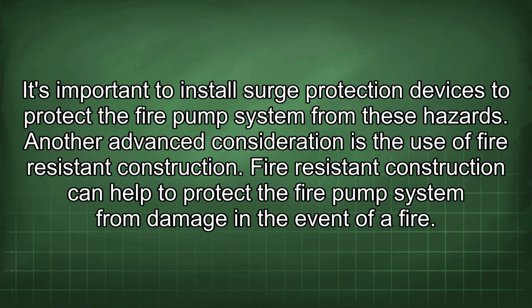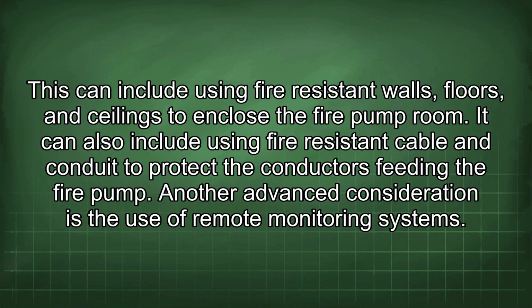Another advanced consideration is the use of fire-resistant construction. Fire-resistant construction can help to protect the fire pump system from damage in the event of a fire. This can include using fire-resistant walls, floors, and ceilings to enclose the fire pump room. It can also include using fire-resistant cable and conduit to protect the conductors feeding the fire pump.